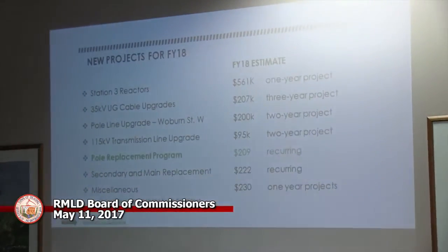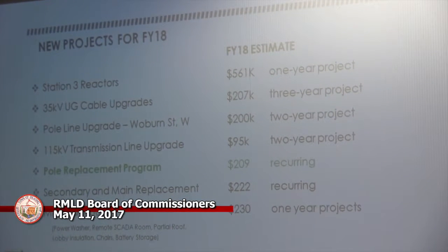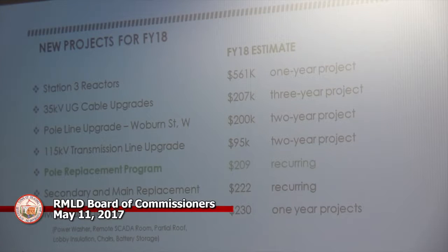This is the Station 3 reactor project, part of the design flow for that substation in order to lower the incident energy and arc energy. To compensate for the transformer impedance, we are installing these reactors - 6 reactors, one set for each transformer, in order to drop the incident energy and make it safer. That's going to cost $561,000. We just had a bid, and you'll be approving it tonight because this is a long lead item, so we wanted to start the bidding process sooner and can start purchasing after July 1st.